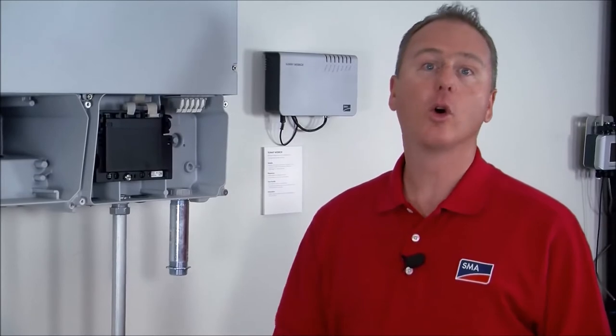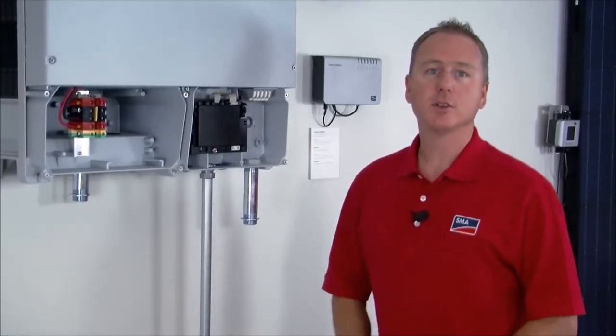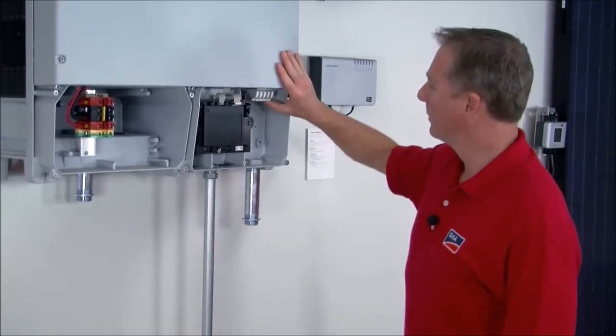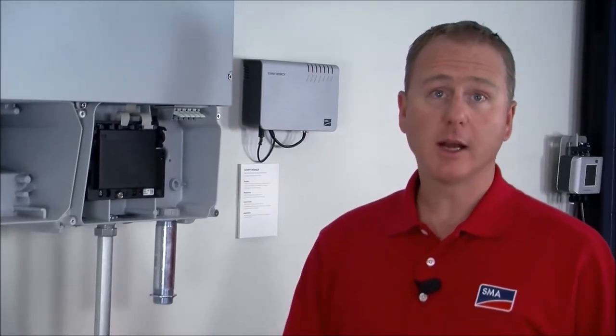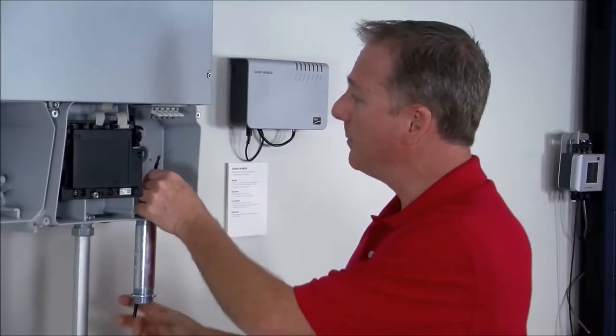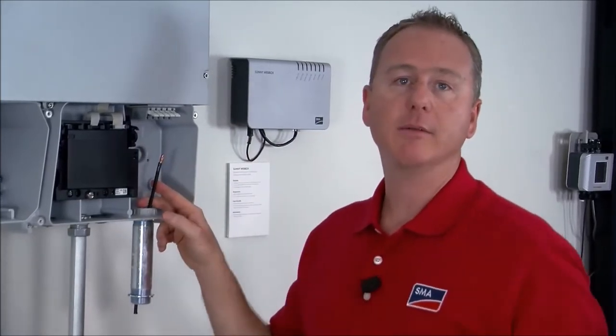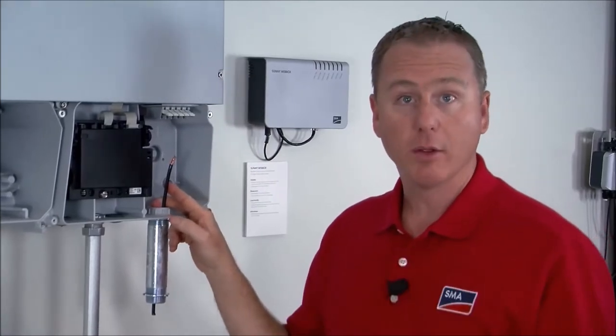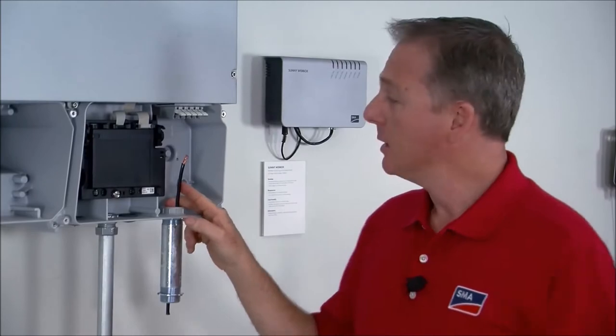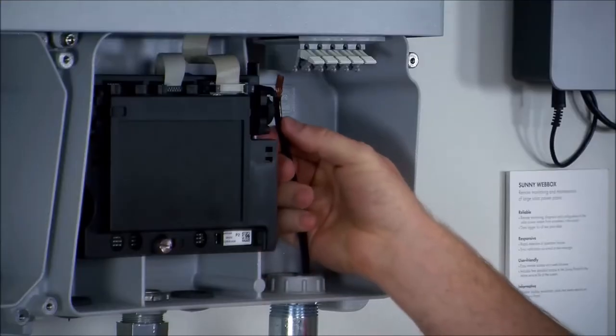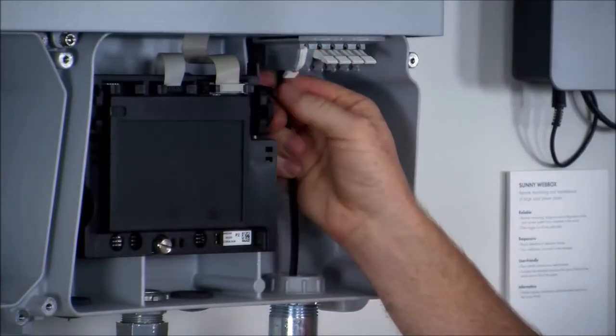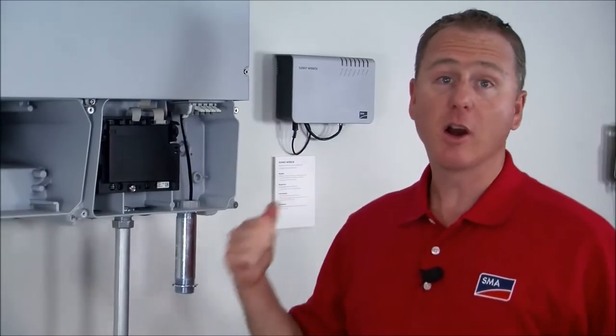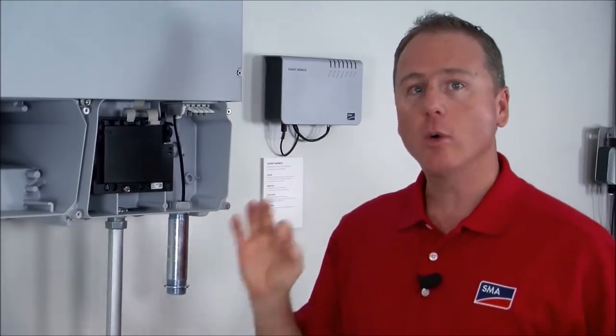So let's start by lifting all the levers on the AC terminals. Now that the terminals are fully open I can insert my conductor. I've got a piece of conduit just here for demonstration purposes but you'd feed your conductor through here and the terminals are clearly labeled on the back plane of the inverter: L1, L2, L3, neutral and equipment ground. So I'm going to put this first wire in the L1 terminal, push it up in there until it won't go any further and clamp it down just like that. Now those conductors aren't moving an inch and again you don't have to worry about torque.